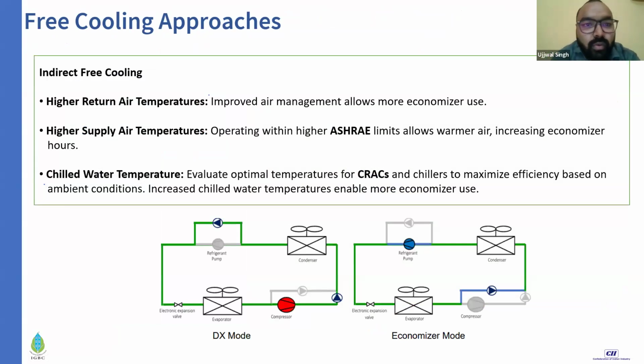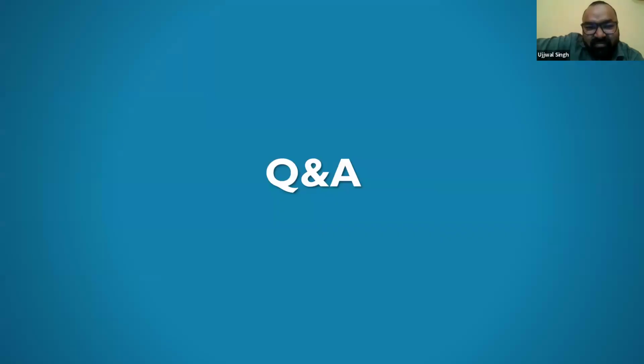There are other methods of free cooling where you can use the indirect method, cooling the refrigerant instead of the air. That refrigerant bypasses your compressor and uses a refrigerant pump instead, as you can see on the right hand side of the drawing. This is one of the methods very common in data centers these days, and has now become an inbuilt feature for most chillers, known as economizer mode. More details on this we will study in the workshop sessions.